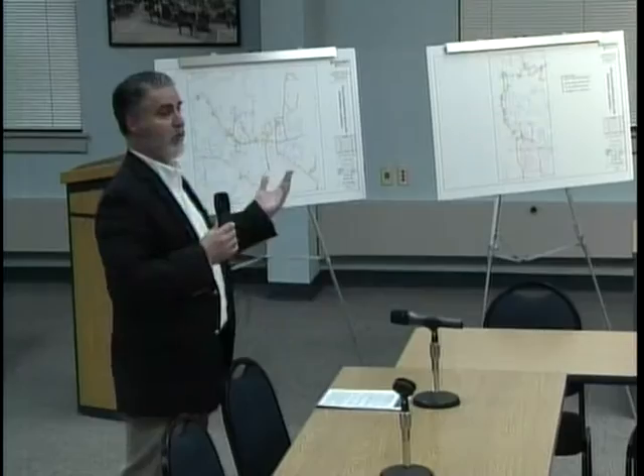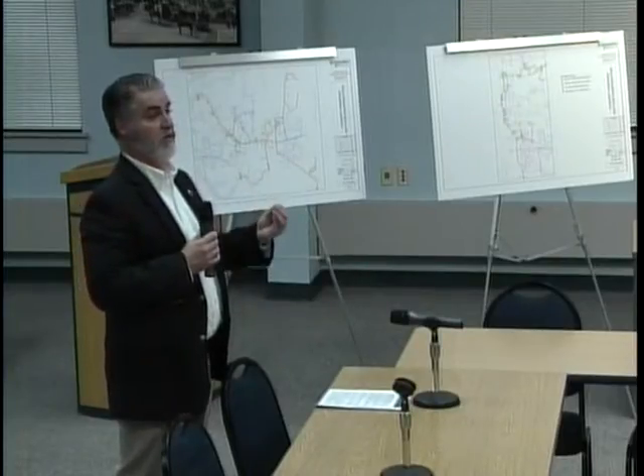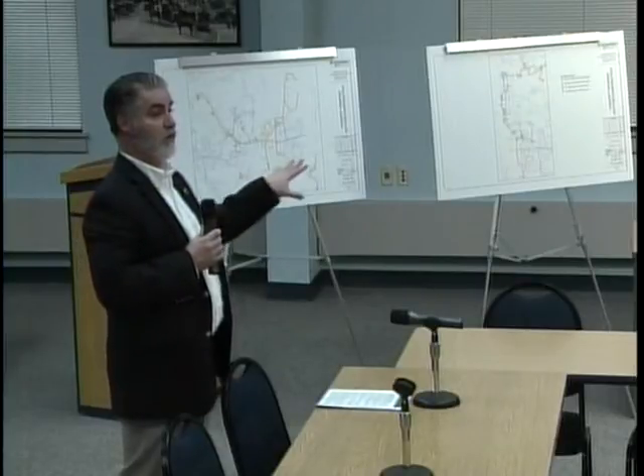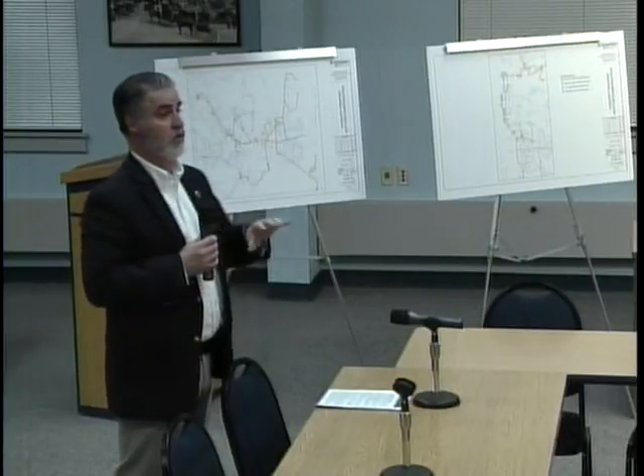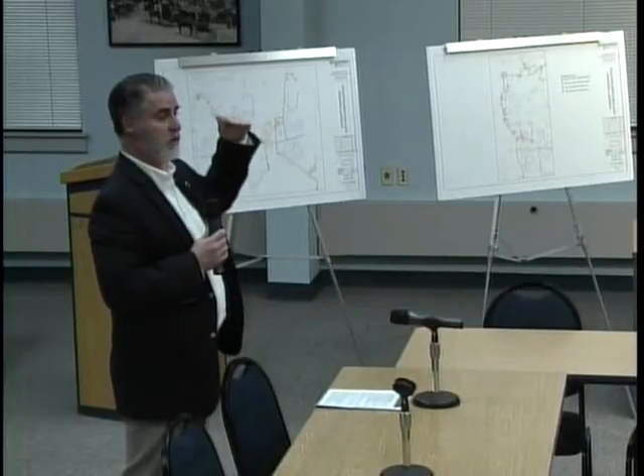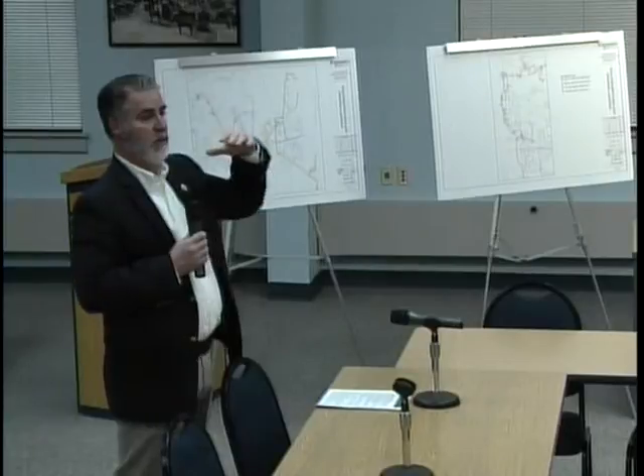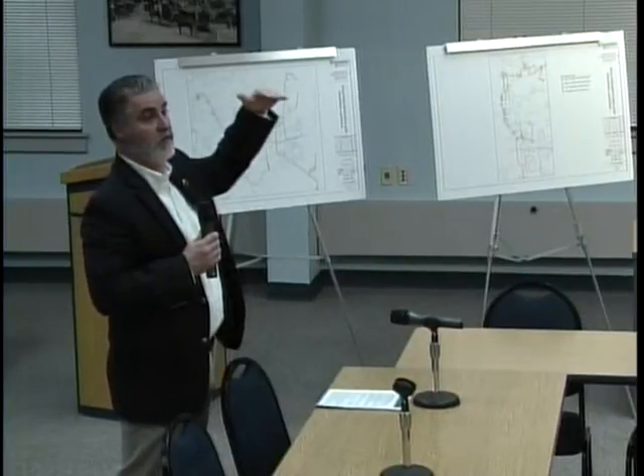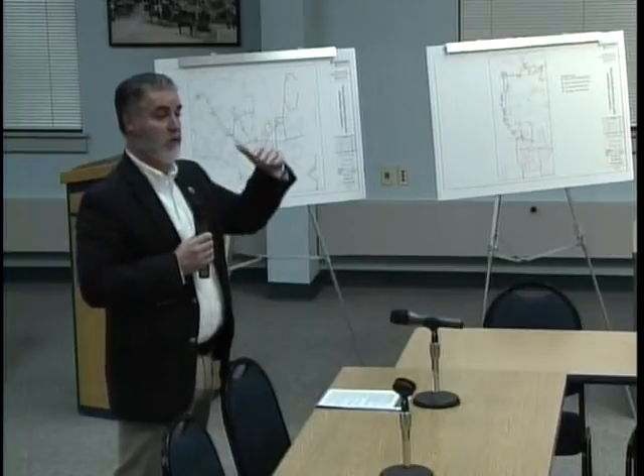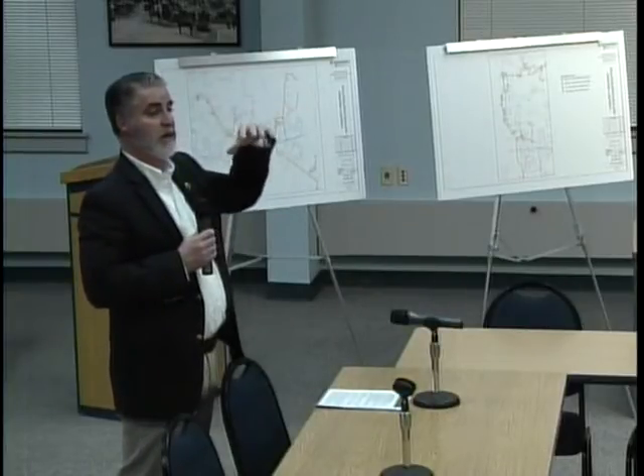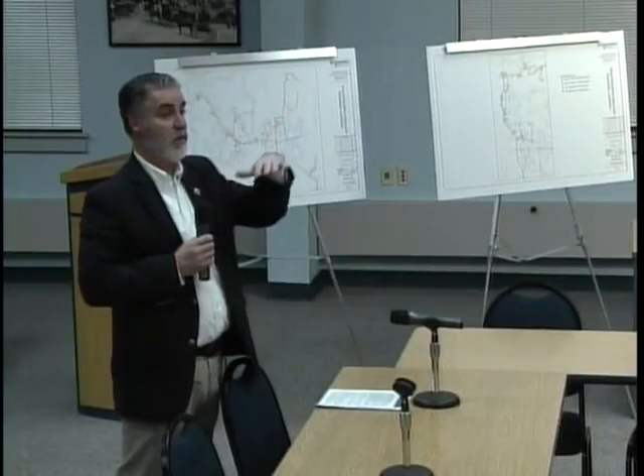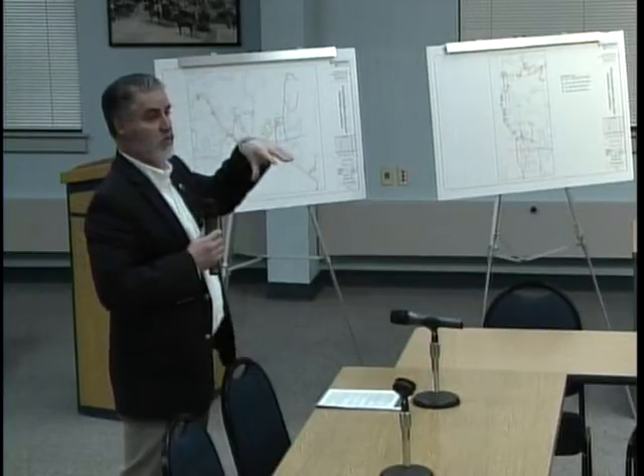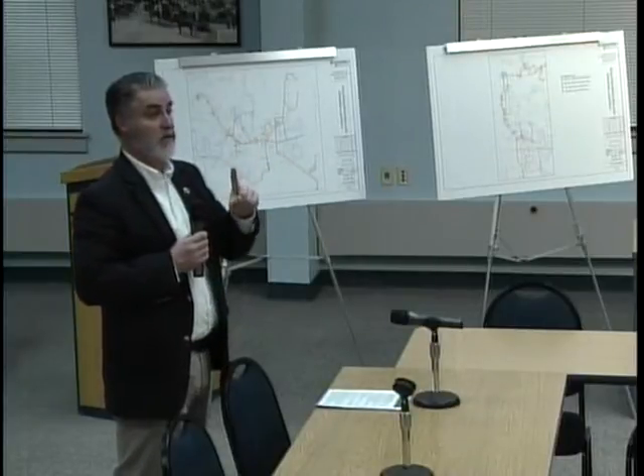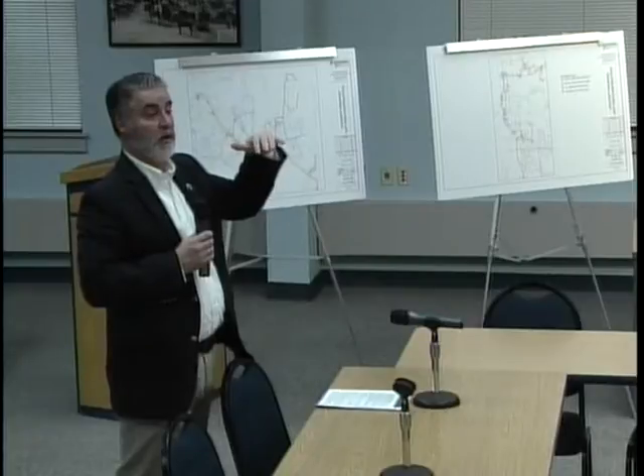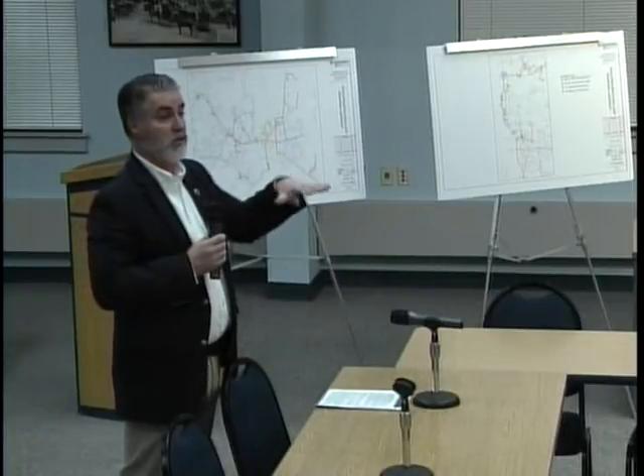That's a good question. Currently, we already run those generators — there's 17.5 megawatts of diesel generation on all the circuits. Those are used for distribution load shedding. When the system is reaching its peak, it has the potential to generate a new ratchet for the system and cost us extra money. If we go over our peak from last year, we'll have to pay extra, and that new peak stays with us for a year. The utility that runs those distributed generators runs them at least once a month to capture and eliminate that peak.